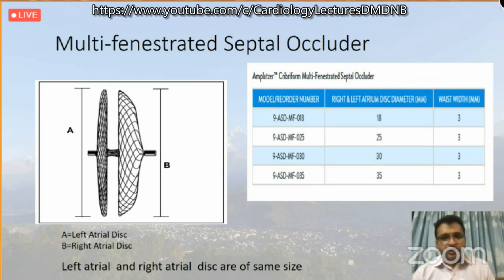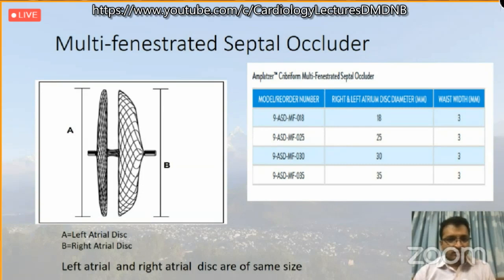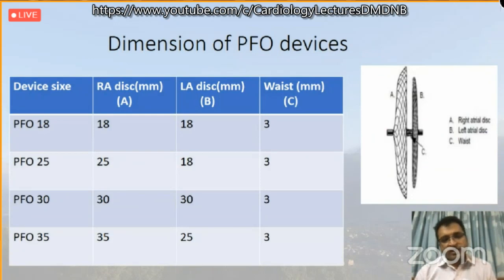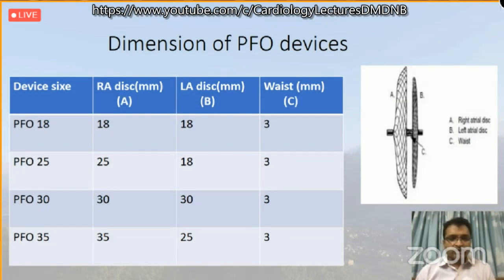Multi-fenestrate septal occluders are used to close multi-fenestrate ASDs. They have a small waist of 3 mm and the device size equals the left atrial disc size; both the right and left atrial discs are the same size. PFO devices: in 25 mm and 35 mm devices the right disc is bigger than the left atrial disc, whereas in 18 mm and 30 mm PFO devices the right and left discs are equal. The waist size is 3 mm in all four PFO devices.